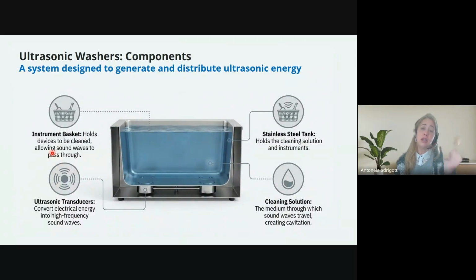So basically, most of the ultrasonic washers work within a specific range of frequency in the ultrasonic range so as to work and to deliver the right energy to the solution and create the cavitation that we need for cleaning our instruments. And last but not least, the cleaning solution, of course, that will contain water and the chemical solution used for cleaning, the detergent.